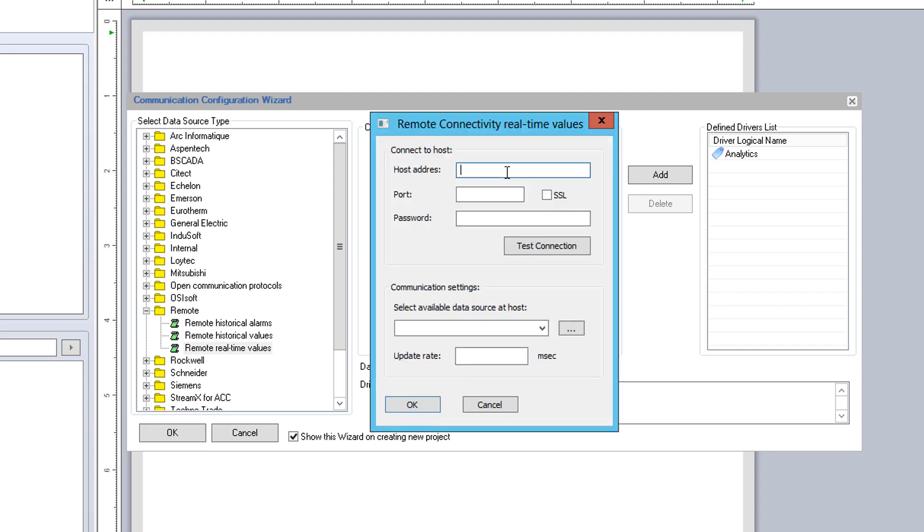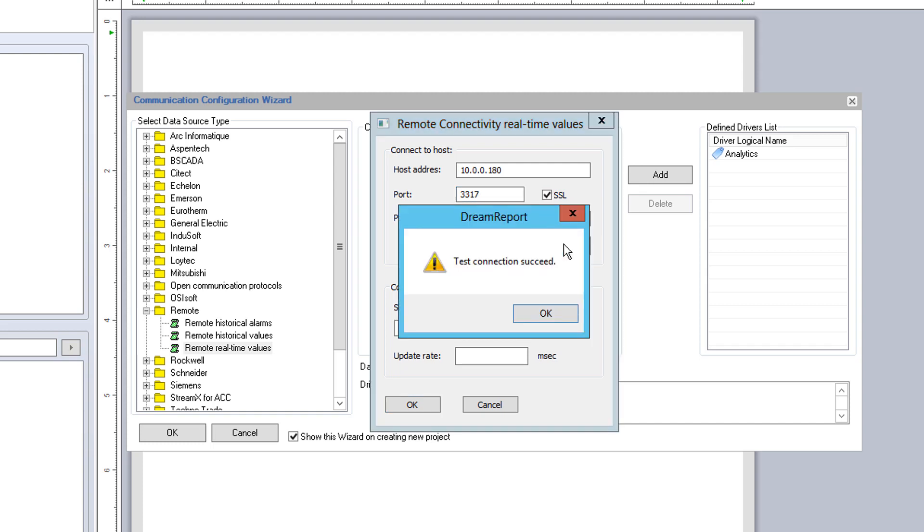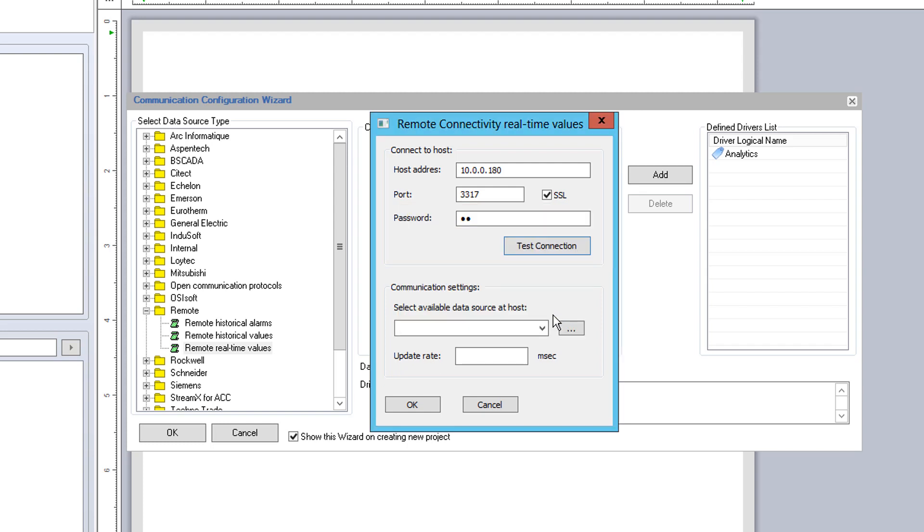You will notice here that instead of choosing a product or platform-specific driver, I go to the Remote folder. I will first set up the connection to the remote real-time values driver. Let me give it a descriptive name and then configure it. Here I enter the IP address of the remote machine, the specified port, SSL if used, and the required password. I will now test the connection. Once connected, I can now select any of the configured remote communication drivers. You see here that only the real-time value driver shows up in the list. I will pick that and set up an update rate of every second.